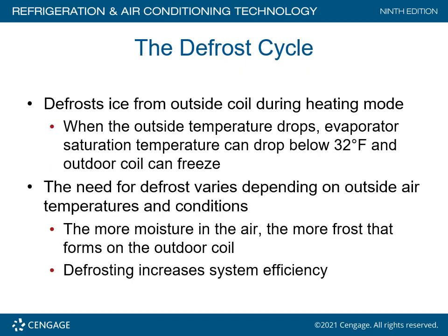Defrost cycle. This is pretty important. Defrost ice from the outdoor coil during the heating mode. When your unit is operating in a cold climate, the outdoor coil during the heating mode is going to ice up. When the outside temperature drops, the evaporator saturation temperature can drop below 32 degrees Fahrenheit, and the outdoor coil starts to freeze. The need to defrost varies depending on the outside temperature and conditions.